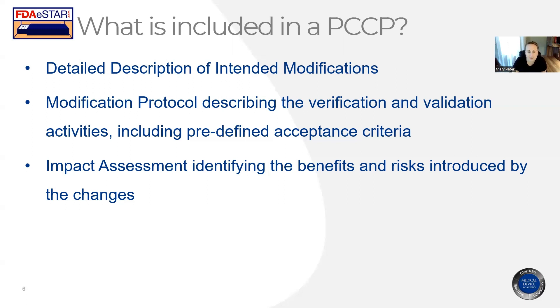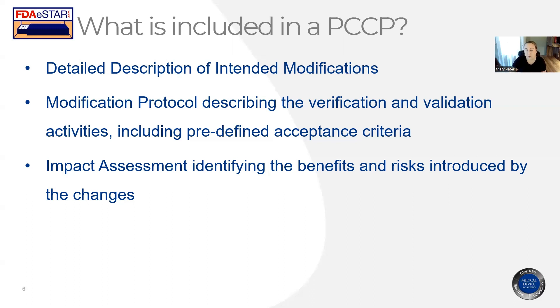Lastly, they would like to see an impact assessment identifying the benefits and risks introduced by the changes, and that would be for each different modification. The guidance document goes into detail for each of these elements, and we have also written a blog available on our website that goes into even more detail on these elements and more information about how to implement a PCCP into your quality management system and change control processes.